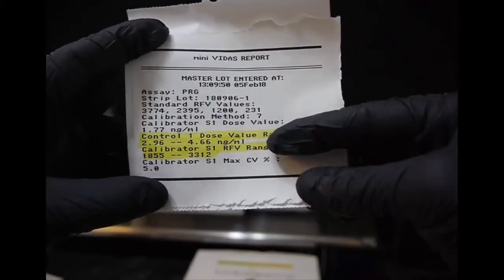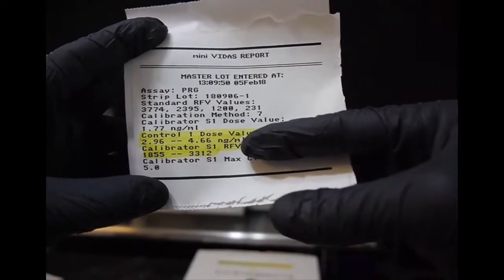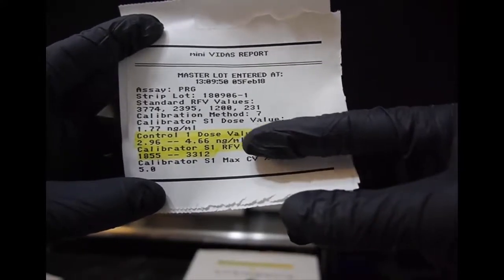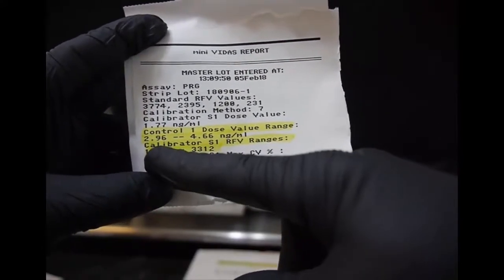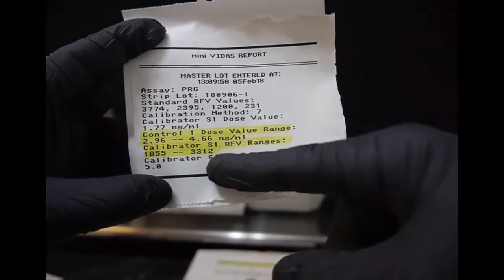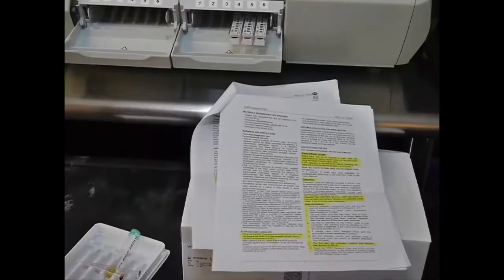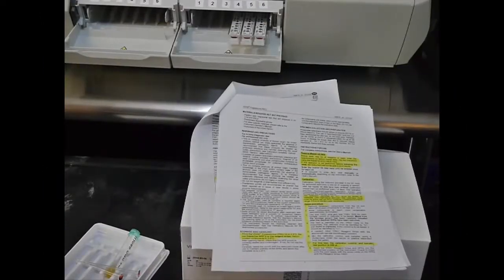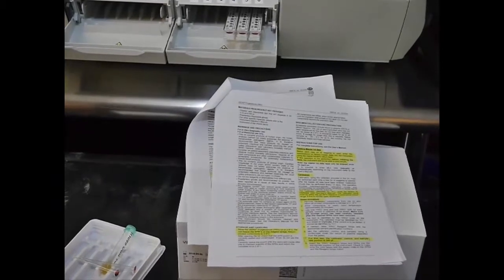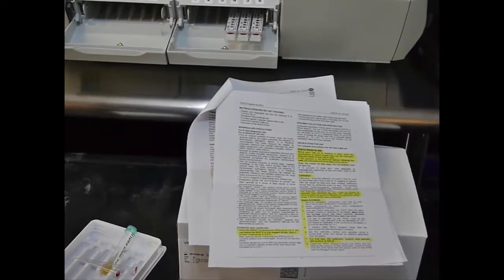The other value provided is the control dose value. That is the white cap vial you will find in your kit. And your controls should come out between 2.96 and 4.66 nanogram per milliliter. The assay insert sheet will also show you the detailed instructions, as you can see highlighted on the paper below, on how to run the calibration. I will go through this with you.